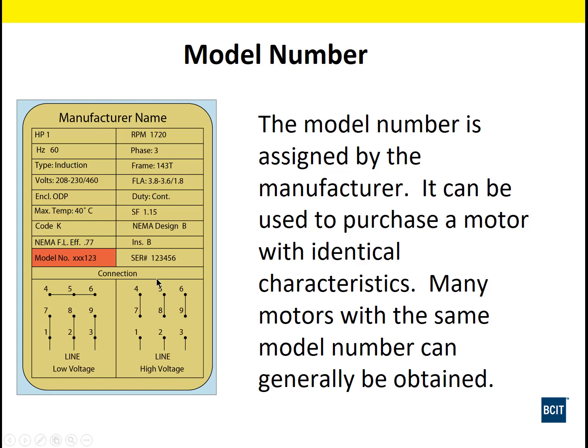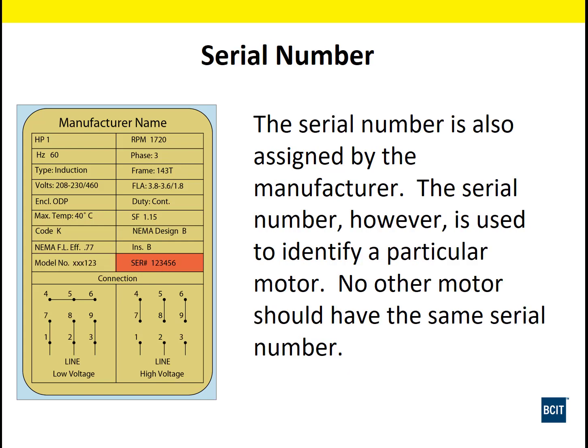Here we have model number. Okay, it's a unique number for a specific model of motor. You may see identical model numbers on multiple motors because they're going to have the same characteristics. It's like having the model number for a car. Our serial number is the number assigned by the manufacturer, so they can identify a particular motor. They can trace that back to the year it was made, time of day and production run that it was made at. So if there's a problem with the motor, they can trace it right back to its manufacturing. And it's a unique number.